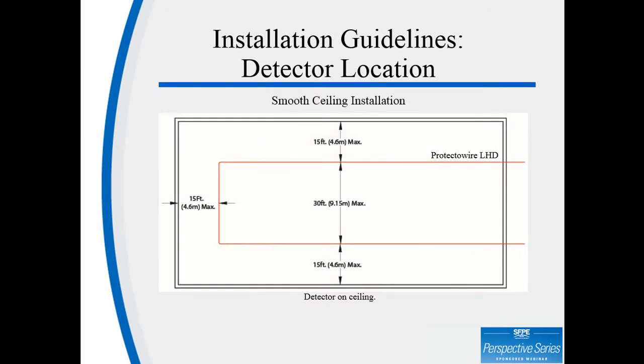LHD detector location on smooth ceilings. On smooth ceilings, the distance between parallel detector runs shall not exceed the maximum listed spacing. There shall be a detector run within a distance of 1/2 the listed spacing measured at a right angle from all walls or partitions that extend to within the top 15% of the ceiling height, as shown in the illustration. This illustration also shows the FM spacing of 30 feet, and that 30 feet can be applied at a 10-foot level.